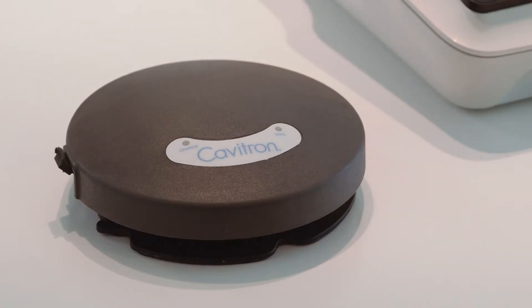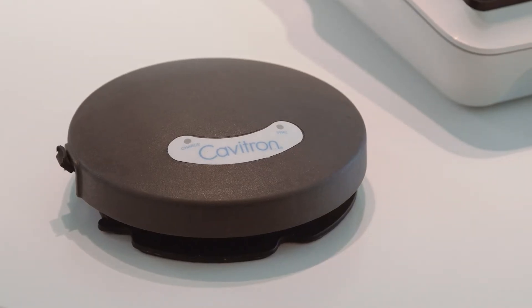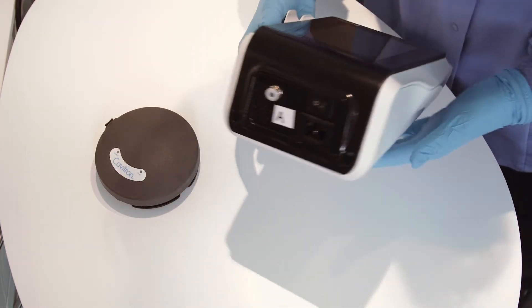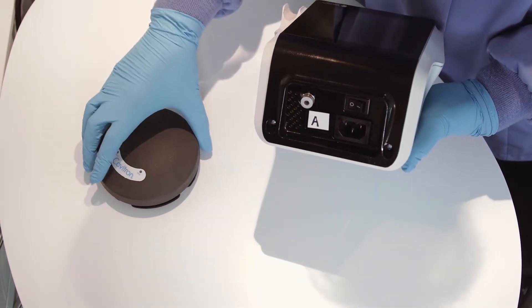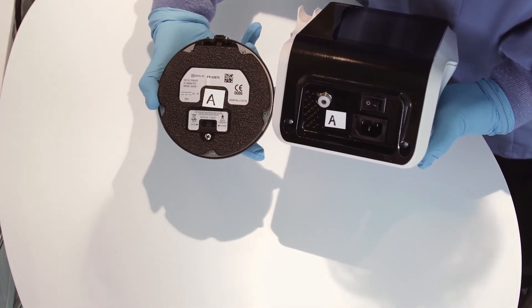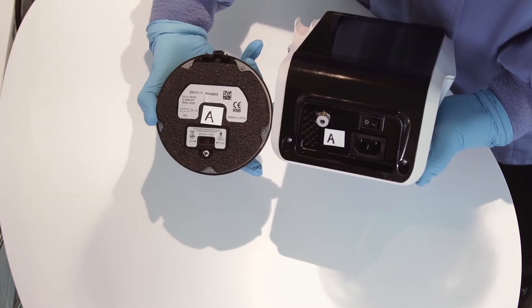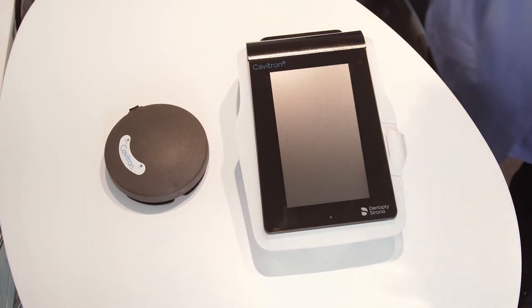The Cavitron 300 Series has been equipped with a tap-on technology wireless foot pedal, which was factory synchronized to operate with the system's base unit. If your office has more than one Cavitron Ultrasonic Scaling System with wireless foot pedals, Dentsply Sirona recommends that you mark the foot pedal and base unit for easy reference as to which foot pedal operates with which base unit.